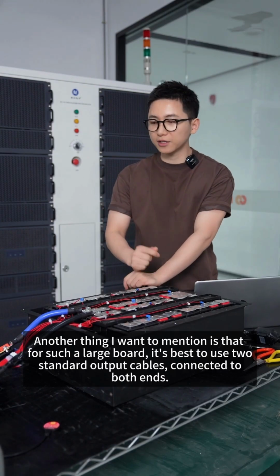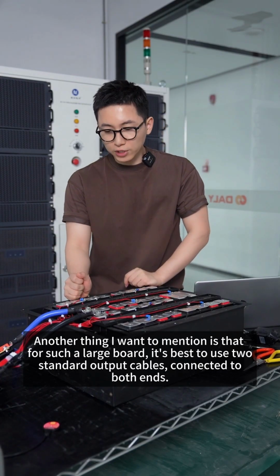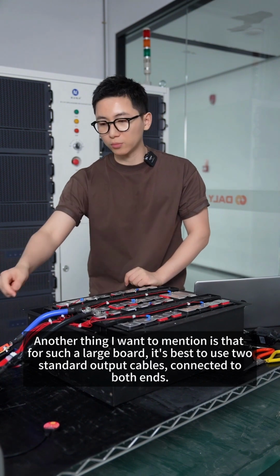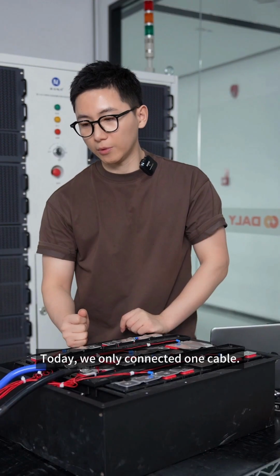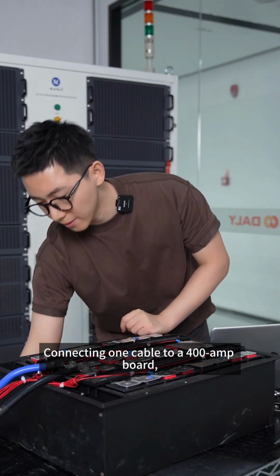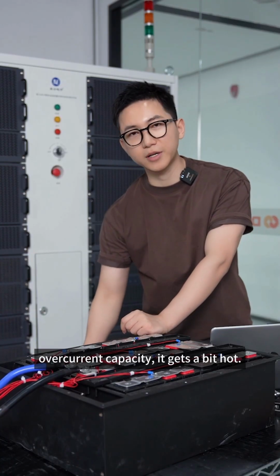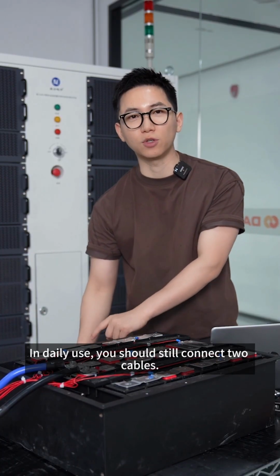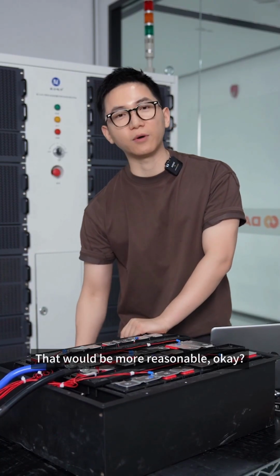Another thing I want to mention is that for such a large board, it's best to use 2 standard output cables connected to both ends. Today, we only connected one cable to a 400 amp board. Honestly, for the cables, over current capacity, it gets a bit hot. In daily use, you should still connect 2 cables. That would be more reasonable, okay?